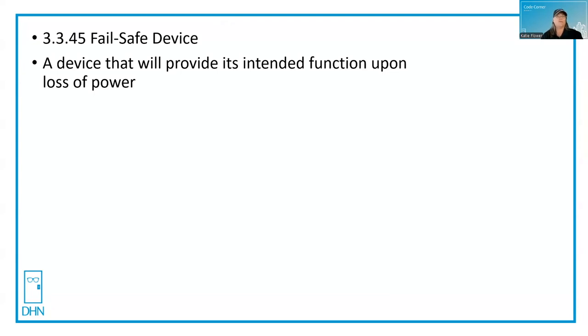For egress purposes, a fail secure lock is locked on the outside and on loss of power it remains locked. But unless we're talking about a specific mag lock that is only fail safe, bored locks, mortise locks, and exit devices can have fail safe or fail secure trim while still providing free egress.